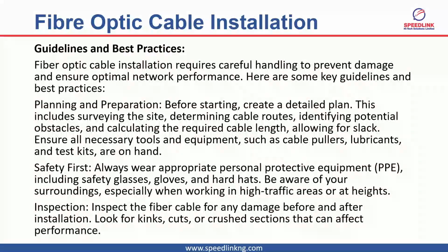For instance, there was a time we were running a cable and it was carelessly laid along the road. A car passed and mashed the cable. It was a soft cable, not really an armored cable. As the car climbed on top of it, it damaged the cable and we didn't even know. It was when we finished terminating the cable and were running traces to confirm, doing the inspection to check if the work was done, that we found out this cable had been damaged, because the trace was not coming out where it should come out.